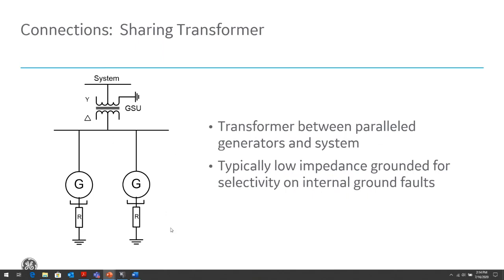The other configuration is sharing through a GSU or a step-up transformer. This is more likely in larger industrial systems where the system might need to be connected to the utility. In this case, the utility requires isolation, so that a fault on their system produces their ground fault current, and a ground fault in the generator is isolated from the system ground. However, the same disadvantage exists here: how do we discriminate which one of these generators the ground fault is on?